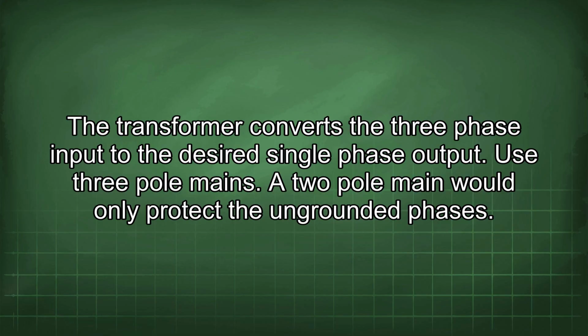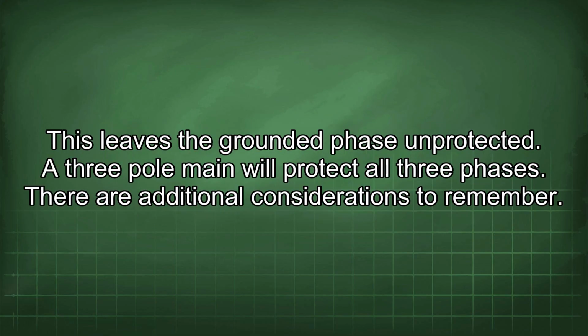Use 3-pole mains. A 2-pole main would only protect the ungrounded phases. This leaves the grounded phase unprotected. A 3-pole main will protect all three phases. There are additional considerations to remember.